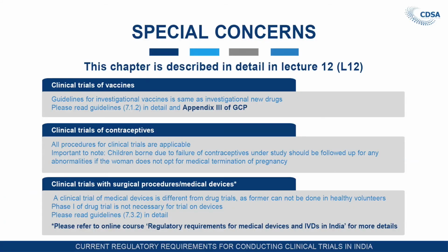One should remember that a clinical trial of a medical device is not the same as that of drug trials, because here you cannot involve healthy volunteers. Phase 1 of drug trials is not necessary for trials on devices. There's a special guideline, 7.3.2, which deals with it in great detail.